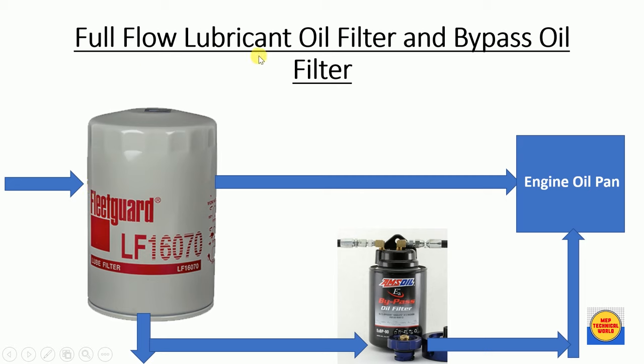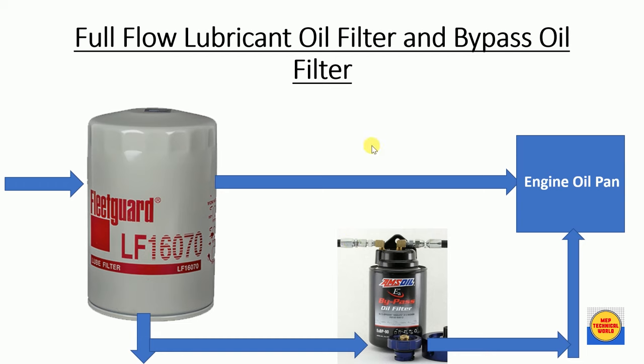Next are the full flow lubricant oil filter and bypass oil filter. The full flow oil filter removes impurities from the lube oil and supplies clean oil to the engine, maintaining frictionless engine parts. If the full flow filter is clogged, the bypass valve opens and lube oil is diverted to the bypass filter and supplied to the engine oil pan, preventing engine overheating and seizure.